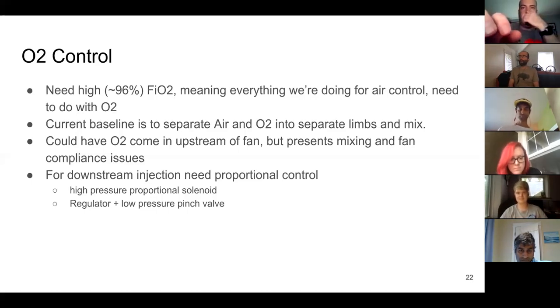We did find fans that are 100% O2 rated, which are used in ventilators. That would simplify some of the controls, but it seems to significantly complicate fan sourcing, and we'd still need an oxygen control valve in that context. So for now, the baseline is to separately control the oxygen from the air and have check valves to prevent the oxygen from going back up into the air, into the fan.